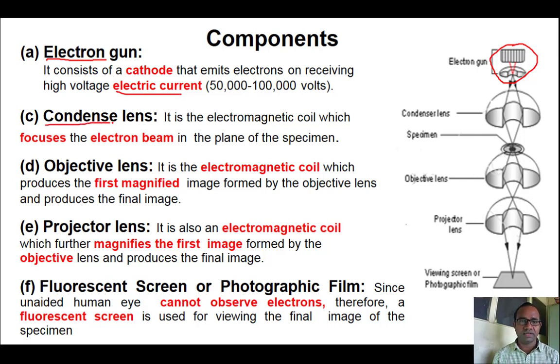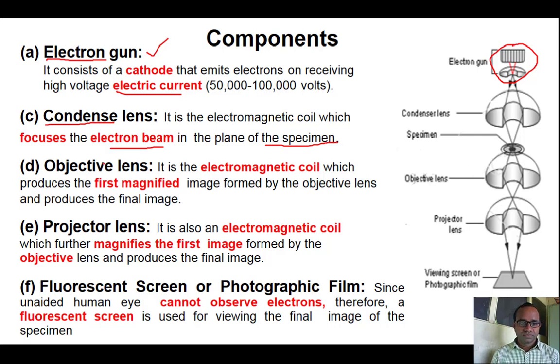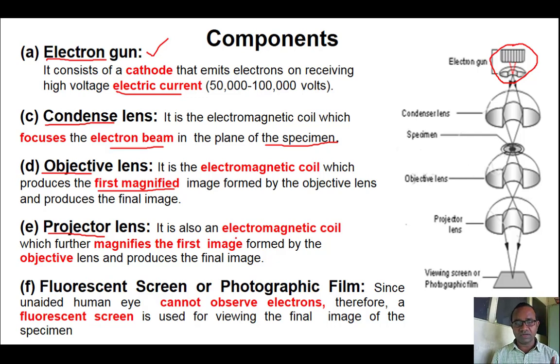The second component is the condenser lens, which is a kind of electromagnetic coil that focuses the electron beam coming from the electron gun onto the sample or specimen. Third is the objective lens, which is also a kind of electromagnetic lens that produces the first magnified image of the sample. The projector lens is another electromagnetic lens that magnifies the first image produced by the objective lens.